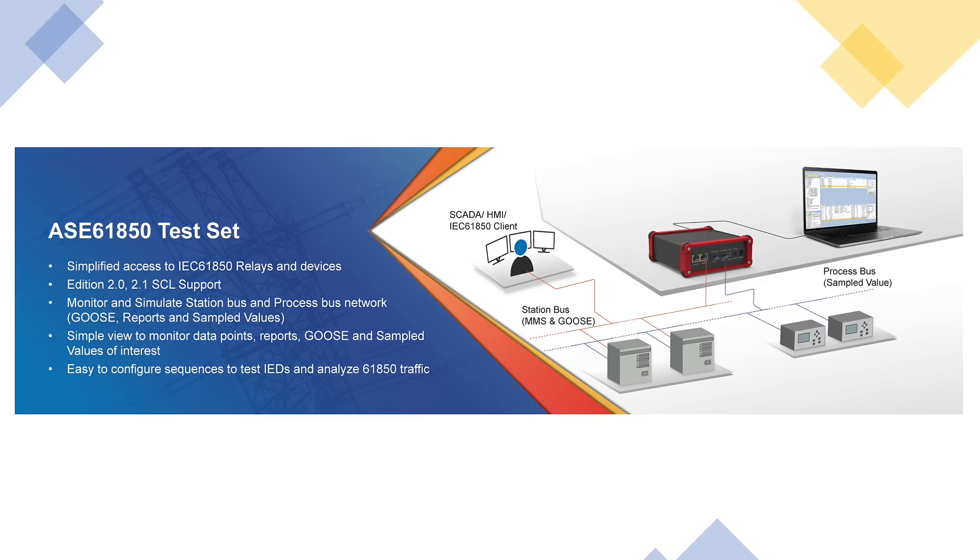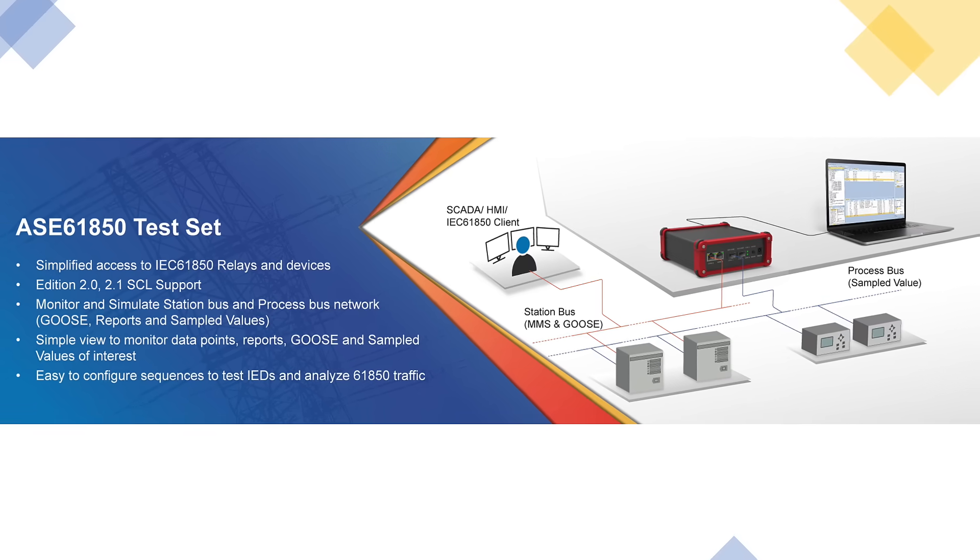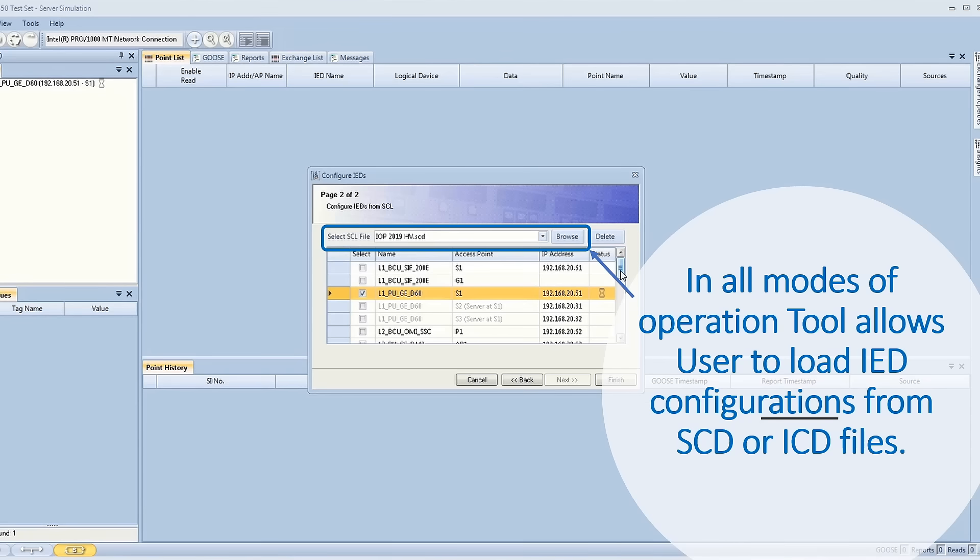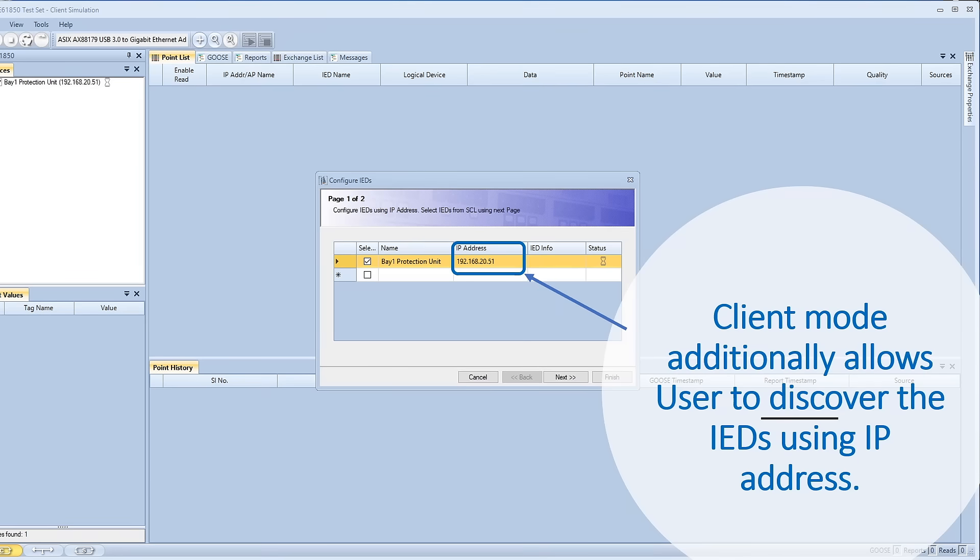ASE 61850 test set supports three modes of operation: Client, server, and monitor mode. In all modes, the tool allows users to load IED configurations from SCD or ICD files. Client mode additionally allows users to discover the IED using IP address.